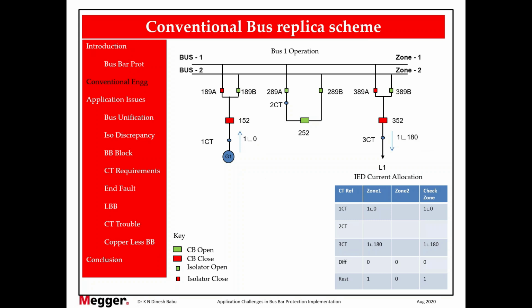There are 4 conditions. First condition: if the CT star point earthing is towards the bus bar and the current is flowing towards the bus bar, the angle would be 0. Second condition: if the CT earthing is away from the bus bar and the current is flowing towards the bus bar, the angle would be 180. Third condition: if the CT earthing is towards the bus bar and the current is flowing away from the bus bar, the angle would be 180. The fourth condition: if the CT is earthed away from the bus bar and the current is flowing away from the bus bar, the angle would be 0.